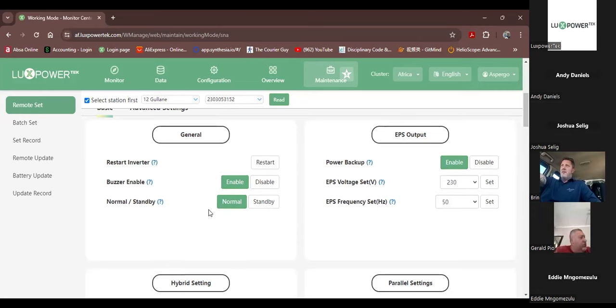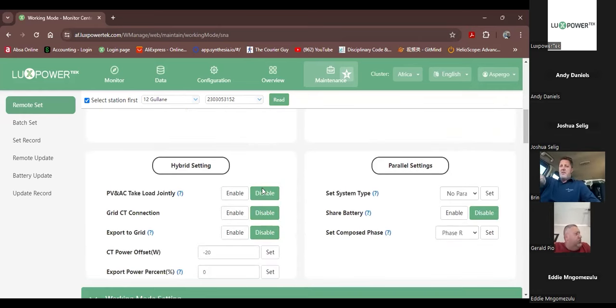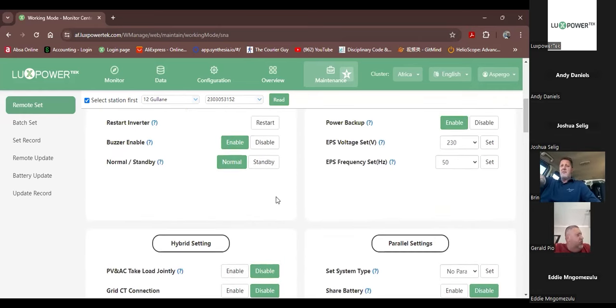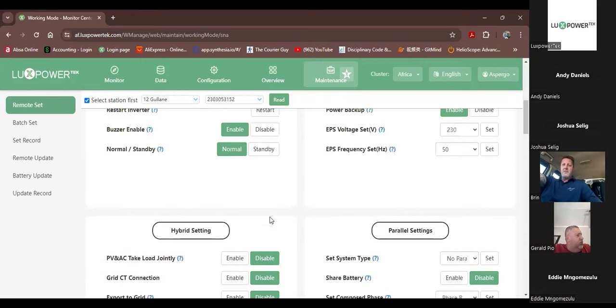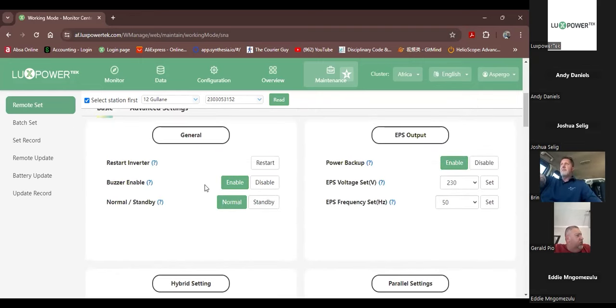So typically you would have to put the machine into standby, and then you can go and change the battery settings. Remember that if the dongle is paired to a router which is running off the EPS output of the machine, then you have to put the changeover switch into the grid position so that you don't lose the Wi-Fi connection. All right, that's very important.